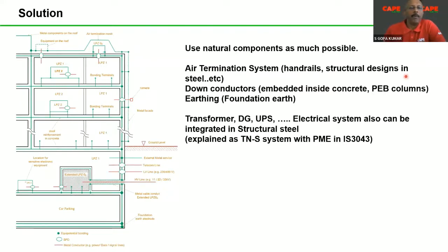Structural designs: a lot of buildings have structural designs, like some architectural design steel materials at the top of the building. We are sometimes forced to keep a rod over and above this structural design, which is practically not required. If your structural design is a steel material, that steel material can work as air termination. A small paint above the steel material you can ignore, which is also written in the standard. This small thickness of the paint, we can ignore it. If you look at the high-rise buildings, most of them have something at the top with some kind of design for aesthetics. So those materials, if they are made of steel, can be used as air termination.